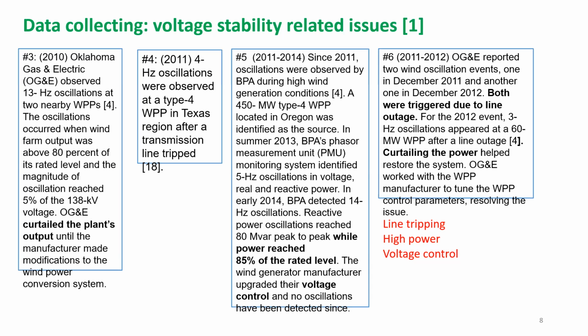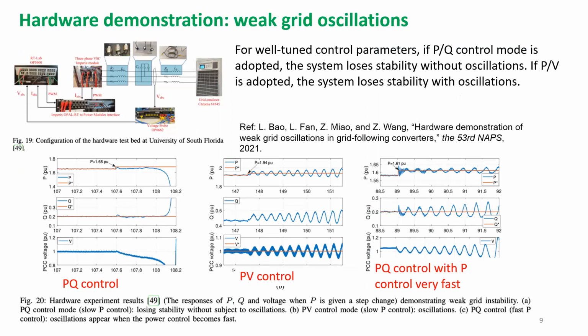The initial guess is that this is a typical voltage stability issue, because voltage stability is when the grid becomes weak and power ramps up, and the voltage collapses. The difference is that oscillation appears instead of direct collapse. With our knowledge of the converter, we can set up a test bed. In our lab, we set up this hardware demonstration with a three-phase voltage source inverter connected to the grid. Everything is hardware, and you can tune the grid and make the parameter large. The SCR, short circuit ratio, is about 2 in this case. Then we keep pushing power to the grid from the inverter.